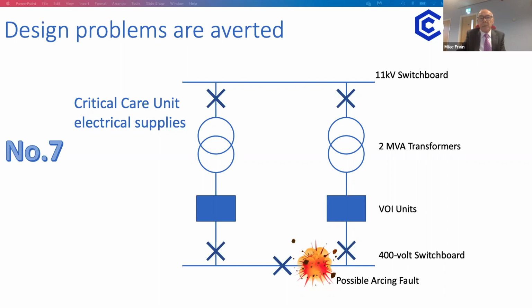By looking into this, I wanted to find out what the dynamic impedance of those voltage optimization units was. And to be quite honest, the results I started getting back, I started to realize that the disconnection times at the LV equipment, even for short circuits, that's bolted short circuit current, or using prospective short circuit currents, wouldn't disconnect very quickly, let alone an arcing fault that might occur at that point. And of course, there's the other question about what a voltage optimization unit is doing in a new critical care unit. Why would you want to lower the voltage in that respect?